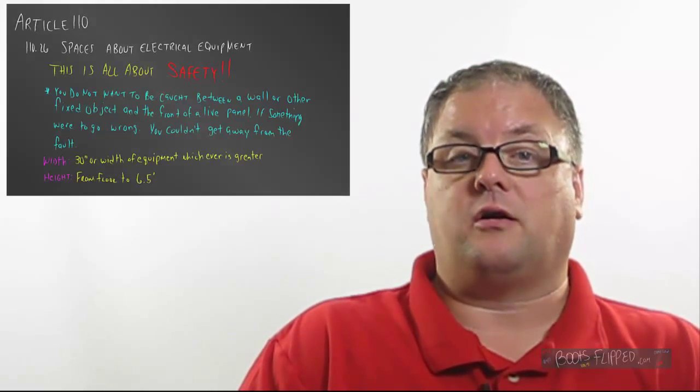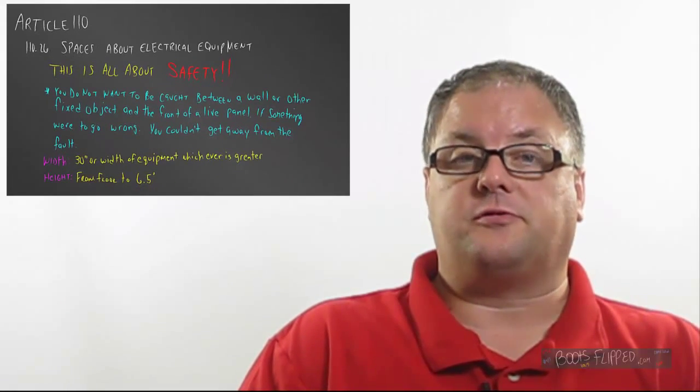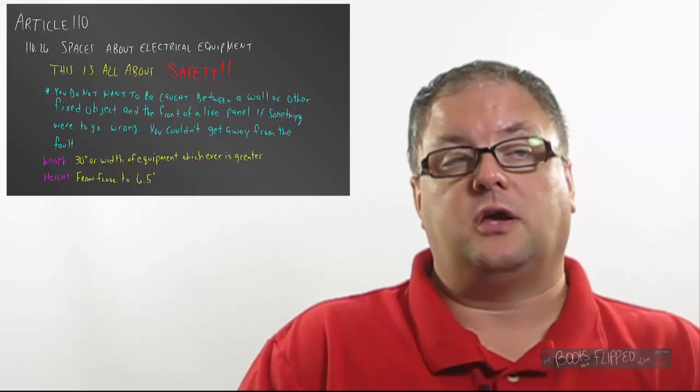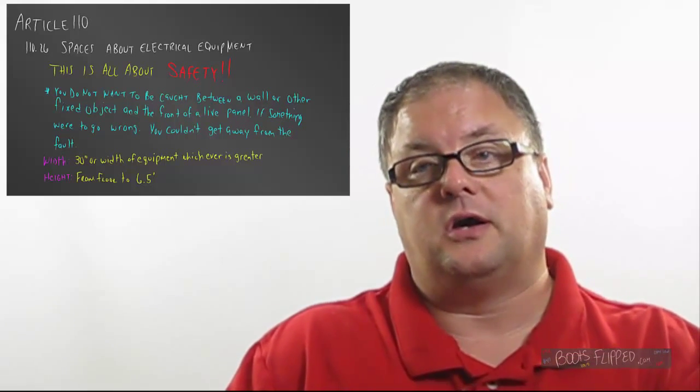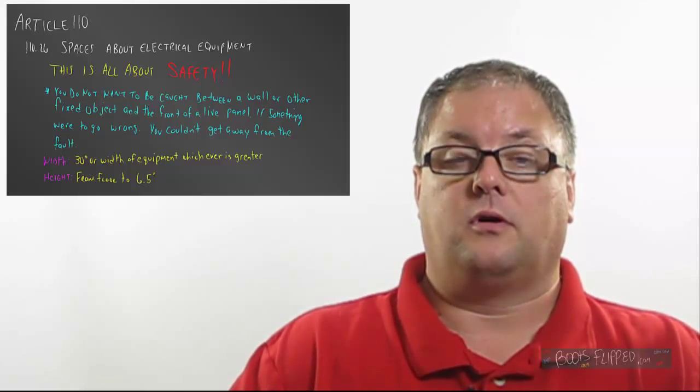Well, we're going to jump a few articles here and go on to Article 110.26, which is Spaces About Our Electrical Equipment. This article is all about safety. And the reason that it's about safety is because we don't want to be caught up between a panel and a wall or some other fixed object if something were to go wrong. So it gives us space requirements. One of the spaces is going to be the width. So 30 inches or however wide the equipment is, whichever is greater. Now, the 30 inches don't start from the center of the panel. It can be from the left panel or the left side and then over to the right side 30 inches. It can be from the right side over to the left side 30 inches. It could be just offset of the center. It really doesn't matter as long as you have 30 inches in width or the width of the equipment.